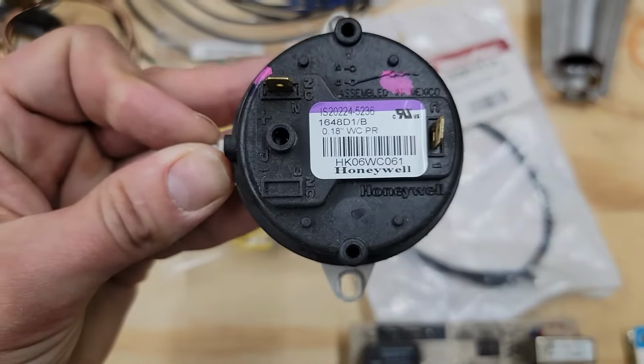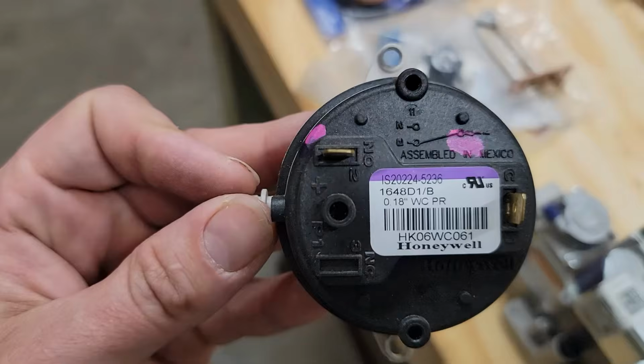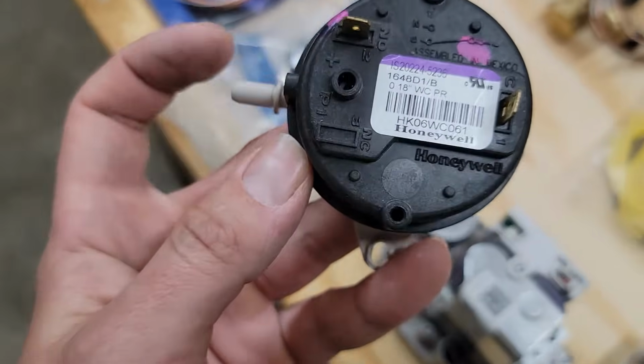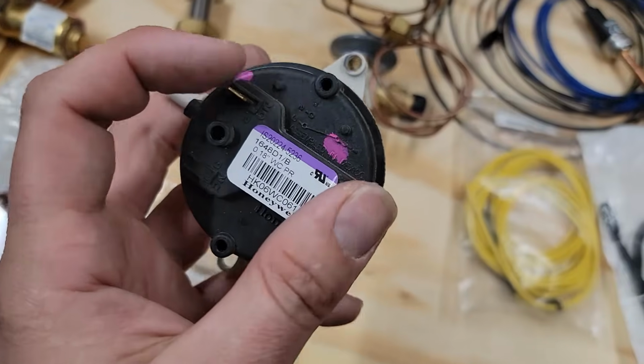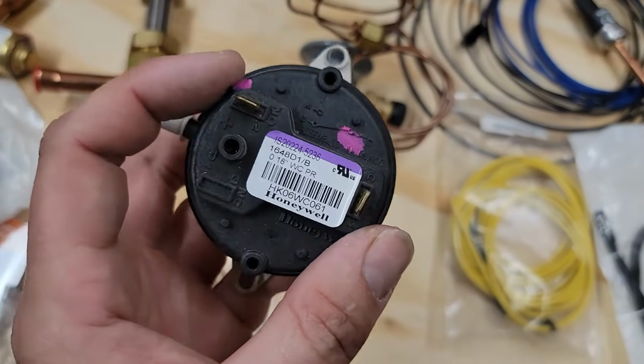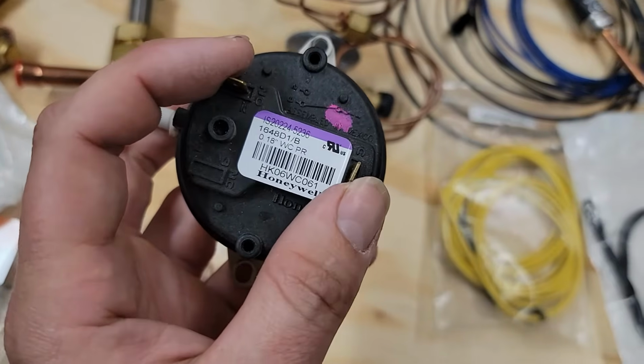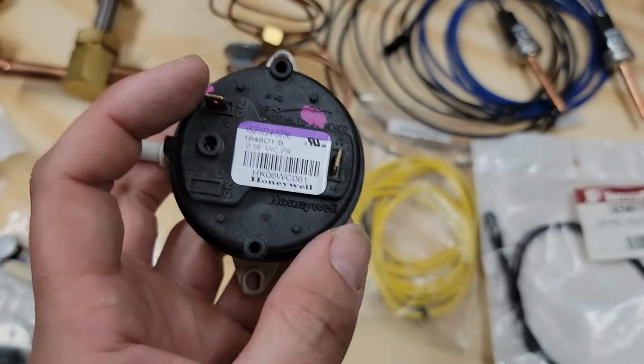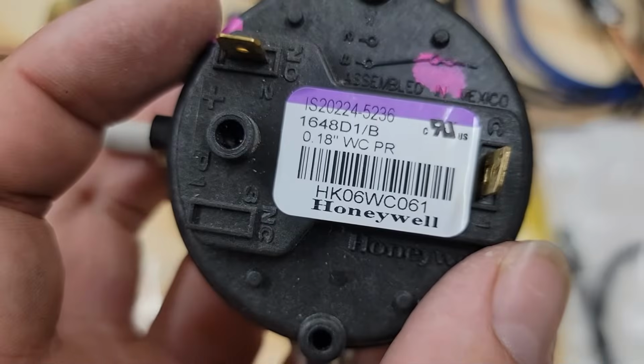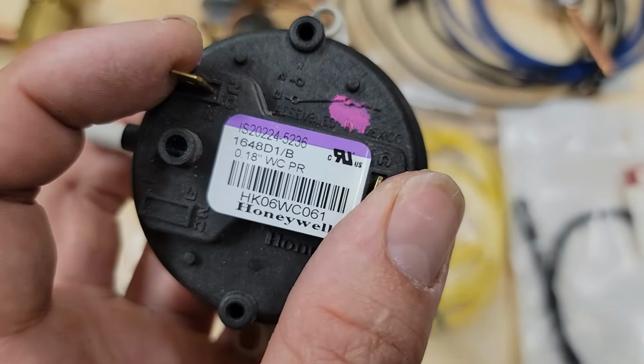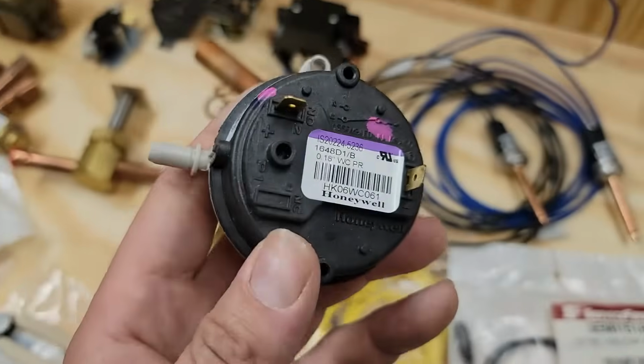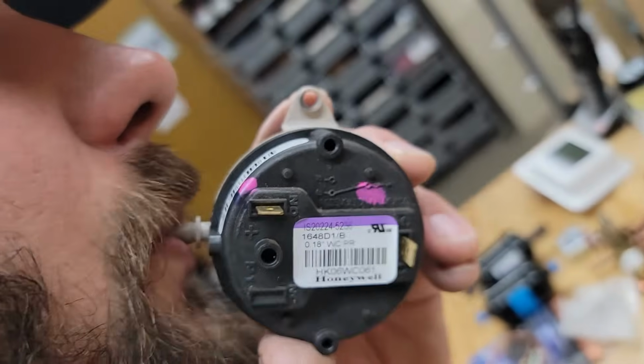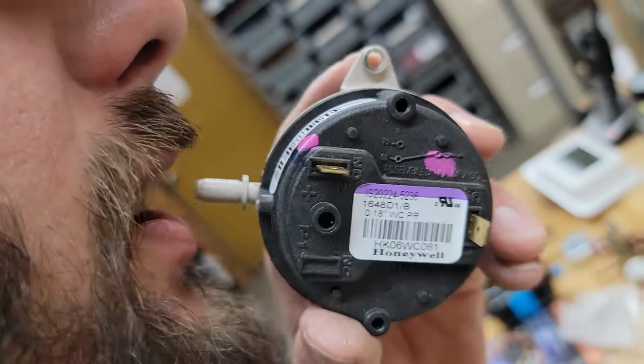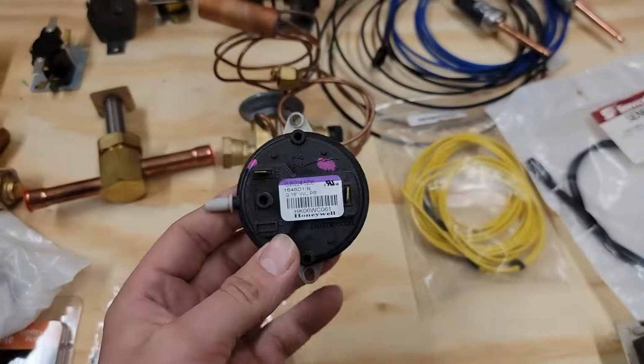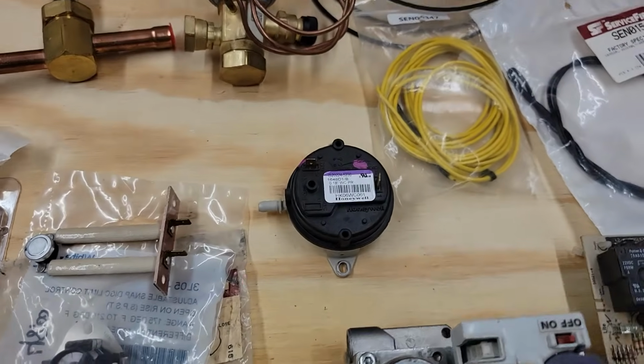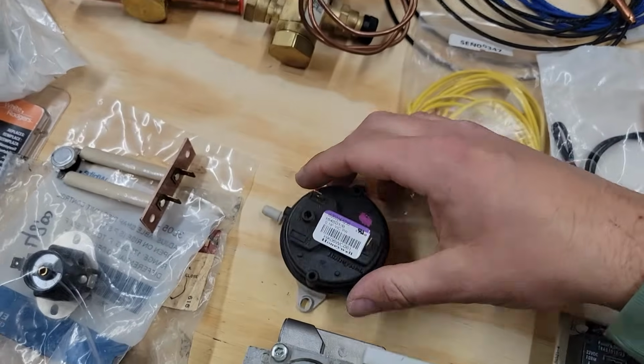This right here is a pressure switch, and usually the pressure switch has a tube, and that tube goes to the inducer motor assembly. And you can see there are 2 wires that go to this, and 24 volts is provided, and normally this switch is open. And whenever the vacuum pulled on the switch is more than 0.18 water column, then this will close. And I will show you how this closes and what it sounds like. Check this out. You hear that? You hear that closing? Now, it's not actually good for the switch, so I don't recommend you do that. But these are very easy to tell if they are working or not.